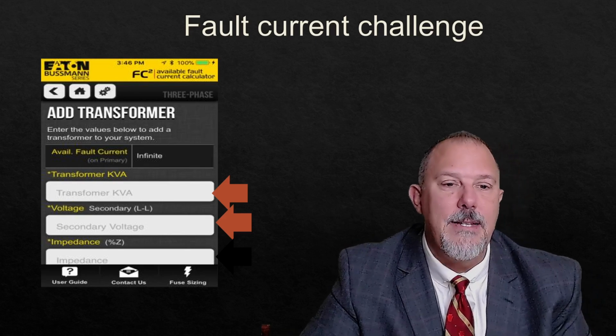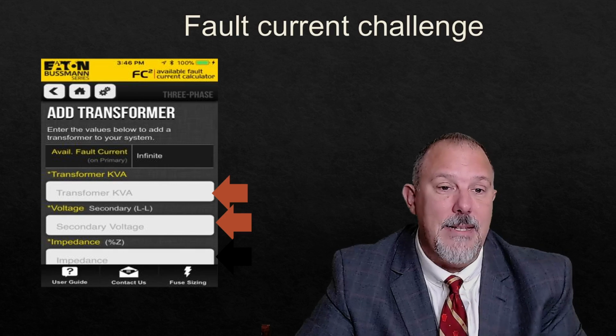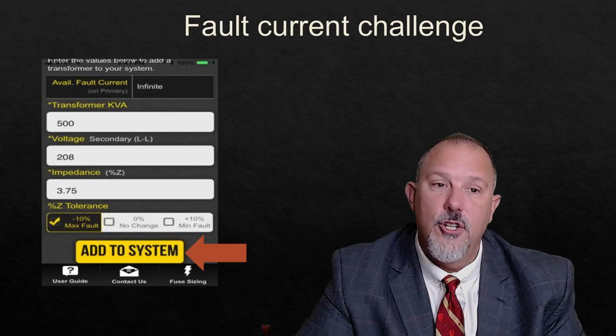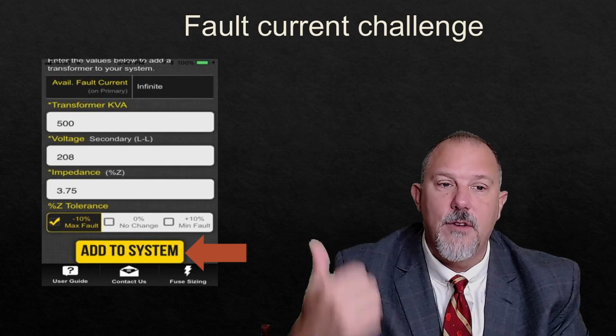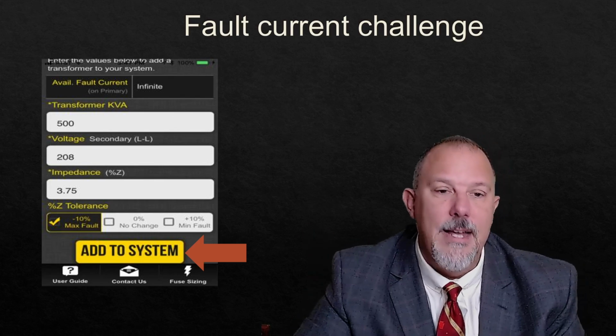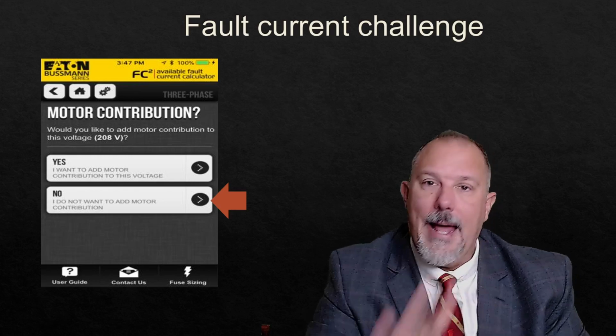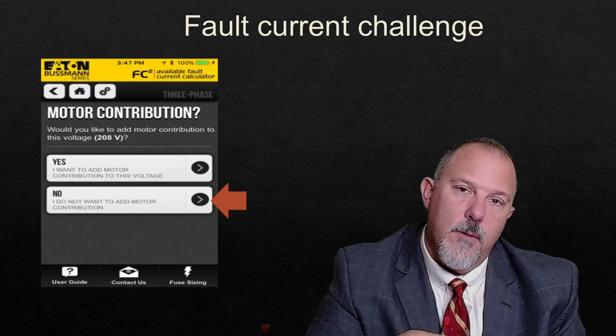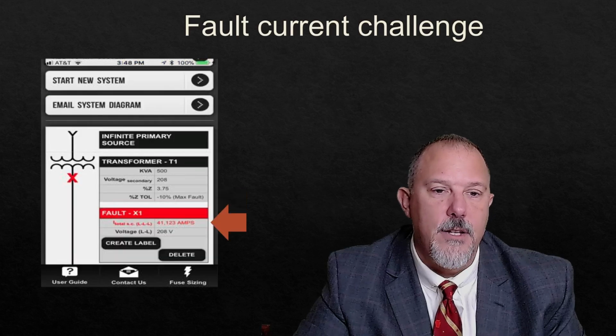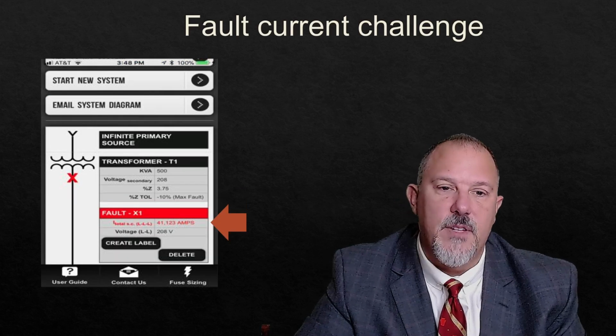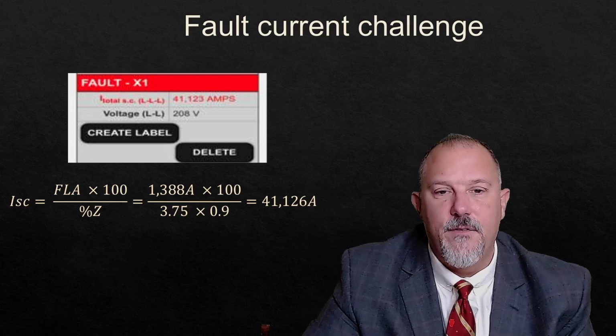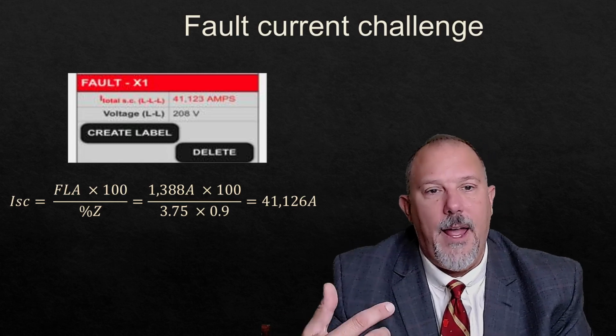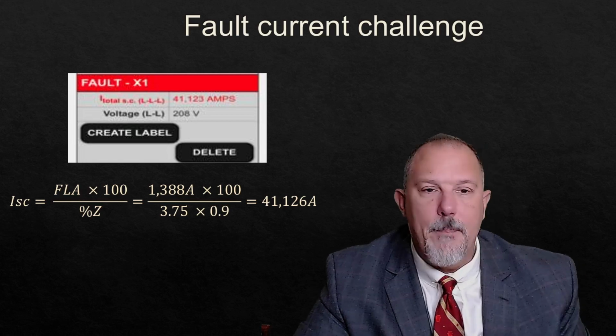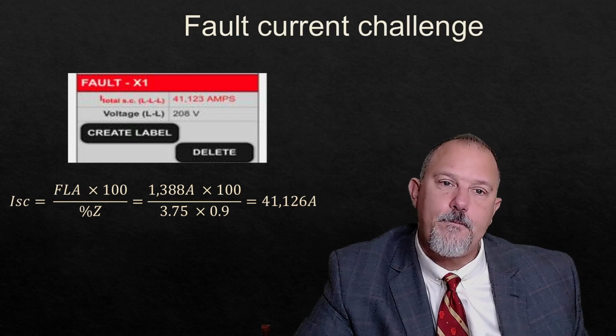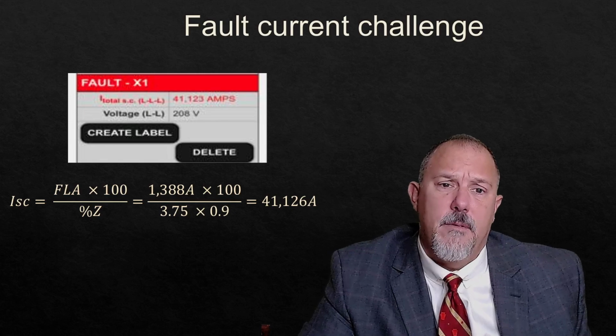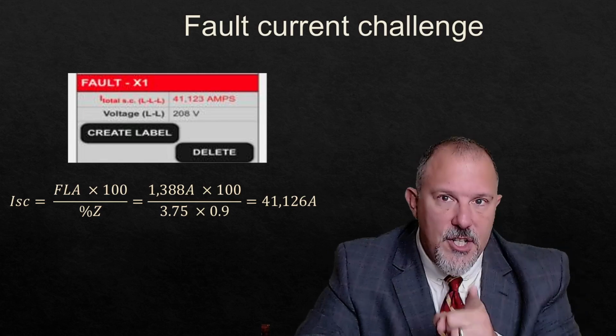I put the kVA in and the secondary voltage and the impedance. So 500 kVA, 208 volts, 3.75, there's the minus 10%. Check that box. Hit add to the system. You can add motor contribution, or you can say, I don't want motor contribution. And we get 41,123 amps. If I compare my manual calculation, I got 41,126, and the app got 41,123. The difference is rounding errors in my math. Piece of cake.